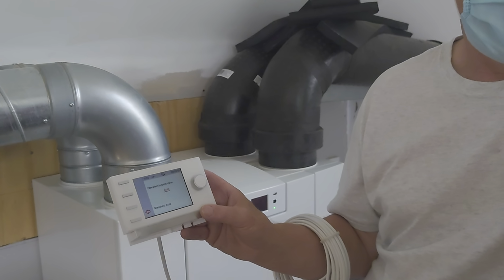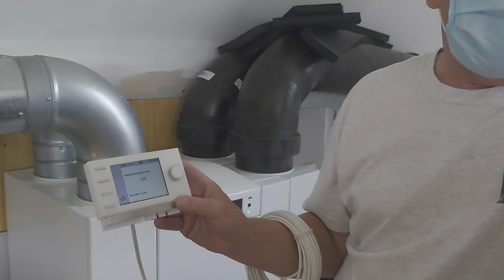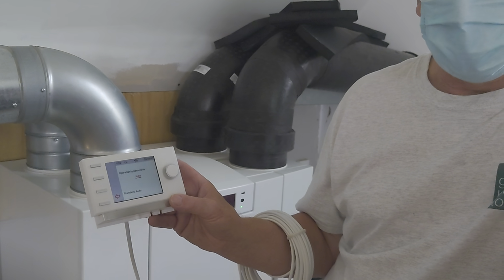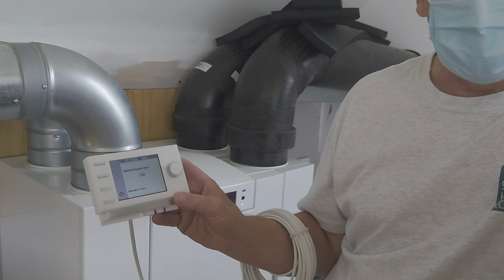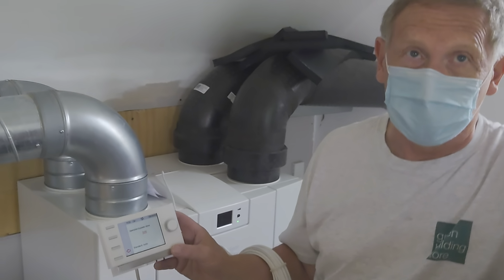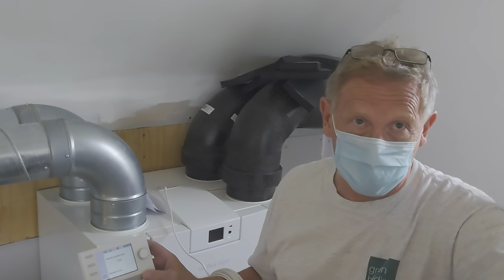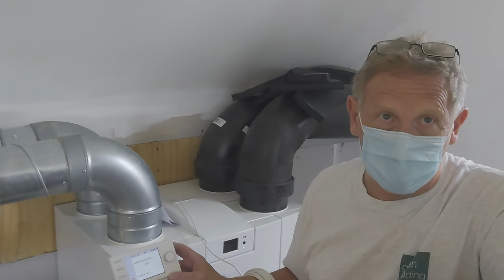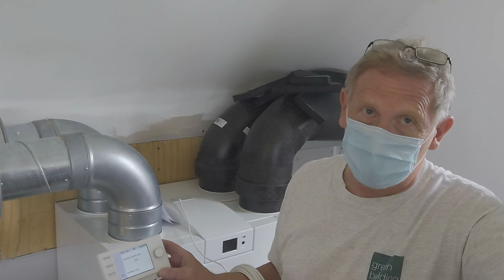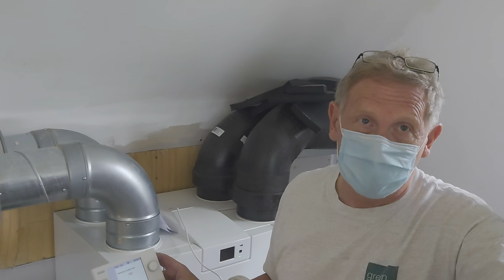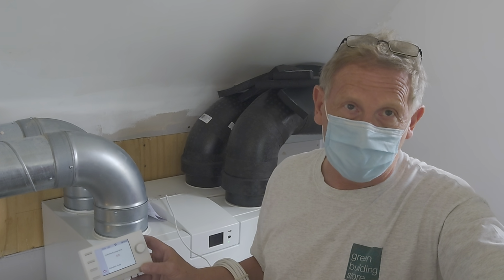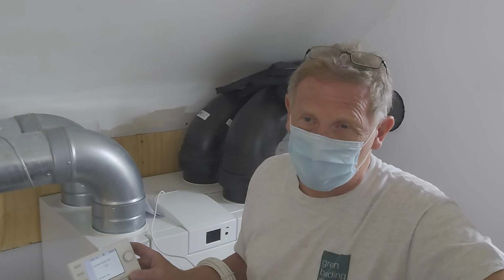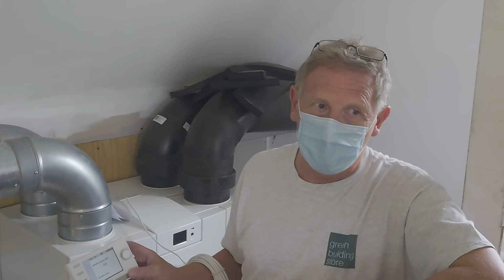But won't it be doing that anyway, regardless of whether the bypass is on? No, in automatic mode it won't go into bypass mode unless it is cooler outside. It always has to be cooler outside than inside. And if it's not, what will happen? It'll carry on bringing fresh air in. It'll be going through the heat exchanger, so it'll still be recovering. When it's cold, does it recover the other way then? It takes heat out of the intake, yes, it can. The heat exchanger works both ways.